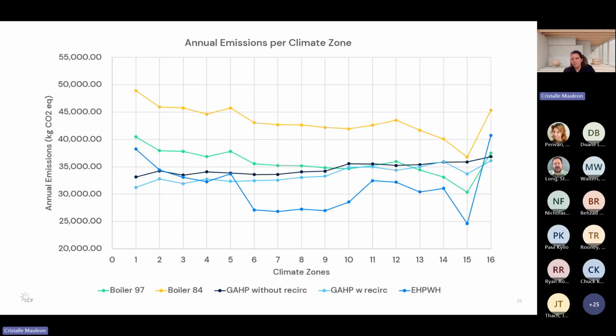The baseline with an 84% efficient boiler shows the highest emissions, while the electric heat pump water heater and the GAHP show significant reductions. In most of the climate zones, the electric heat pump water heater has the lowest emissions, especially in the zones that have cleaner grid electricity. In a couple of the colder zones, the GAHP without recirculation sometimes outperforms the electric heat pump water heater in emissions due to the hourly emissions factors in those climate zones.